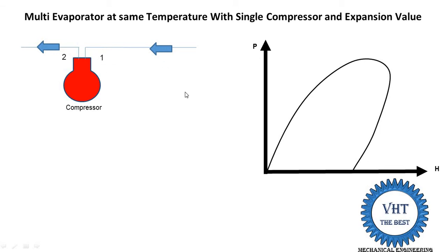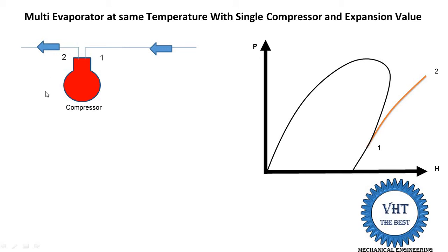Point number one is the saturated vapor at low pressure, so point 1 is on the vapor line at the bottom region. Point number two — pressure is increased, so point 2 moves upward; temperature is increased so enthalpy is also increased, but entropy remains constant. The constant entropy line on the P-h diagram is drawn as a curve, so this is our point number 2.